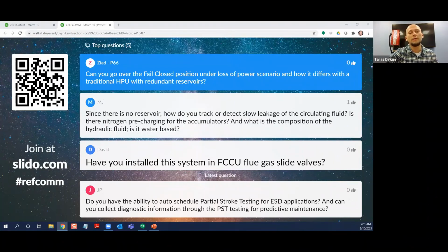So basically, if you require fail close on loss of power, we would have to provide an additional accumulator or reservoir, which would operate with the solenoid valves, which can be separate from the ESD system. However, it can also be combined with it. So this is basically just looking into different variations and making sure how you want your actuator to operate. However, if you're talking about current setups, we would have the separate ESD system, which would trigger the ESD function. And then whenever you require fail close on loss of power to the actual controller, there would probably be a separate system and separate accumulator system, which you would charge before that. However, for this particular application on all the FCCU slide valves, we just require to fail last on loss of power. Like currently, our HPCUs do the same thing. It doesn't actually go fail close. It usually stays put in 99% of the actual cases.